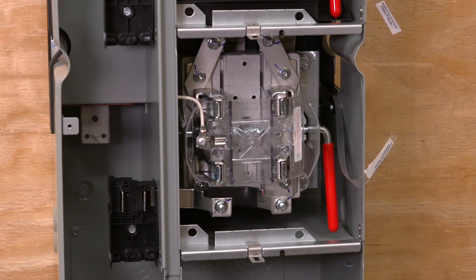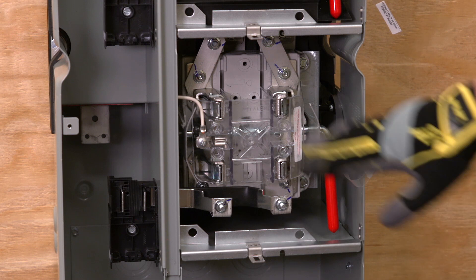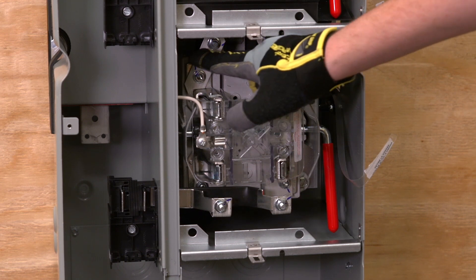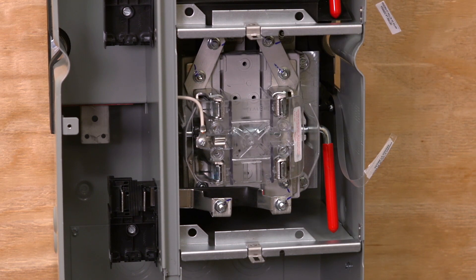In 125 amp stacks that have three incoming phases and a single phase out, the meter positions can be re-phased in the field. Keep in mind this does not apply to the 225 amp lever bypass stacks which must be factory phased.